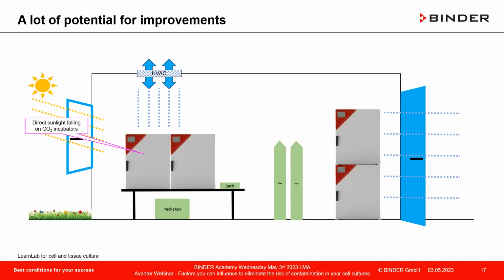That heat then is transferred into the chamber, and then you have an increase of temperature, usually 37 degrees C if we're working with mammalian cells, and then you have an over-temperature shooting, and it's going to leave the CO2 incubator. Here it does not have a cooling unit, so it's very, very slow. And if too much sun rays are falling on the outer housing, you have an increase of the internal temperature drifting away, and that is not good for good growth. So that's one thing you can change immediately.